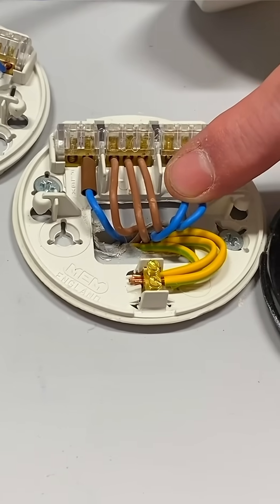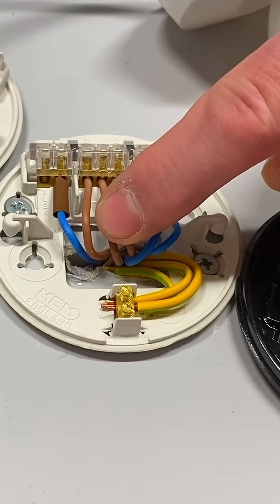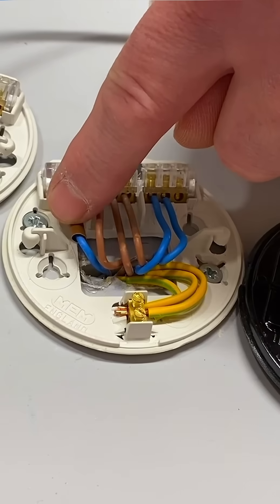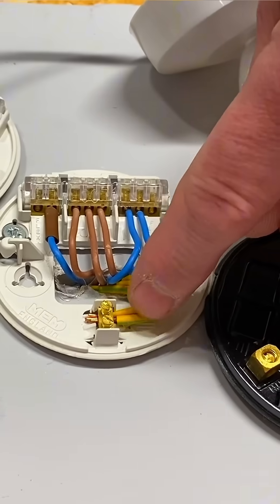We've got our neutral coming in and our neutral going out to another room. We've got a permanent live coming in, a permanent live coming out, a permanent live down to the switch, and a blue conductor identified with brown sleeving — which isn't a neutral, it's our switching line conductor coming back. And we've got our connections for our circuit protective conductors.